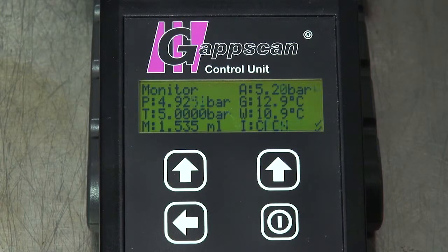If the heat exchanger shows a defect above 20 microns, it is important to know whether this relates to one major defect or several minor defects, and testing at a lower pressure will assess this. You can also use the lower pressure when the leak is discovered to be so large that the test period would be unreasonably short. At a lower pressure, the rate of loss should be lower and so the test period will be extended. The control unit is in monitor mode.